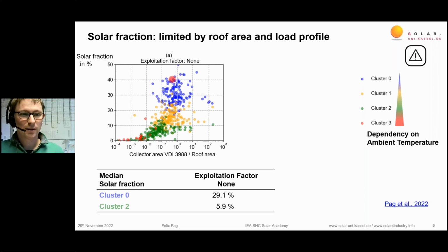Blue dots represent load profiles that are quite flat, with high summer heat demand, allowing us to reach a high solar fraction of 30 to 40%. But the more seasonal the heat load profile is, the smaller the solar fraction, if we design the solar collector field according to summer heat demand.